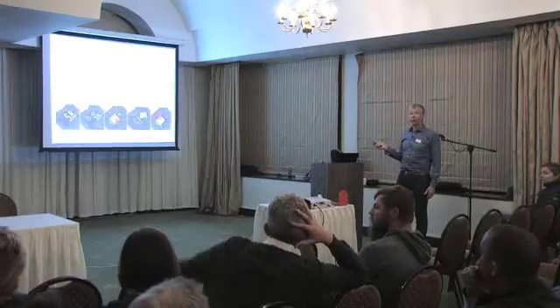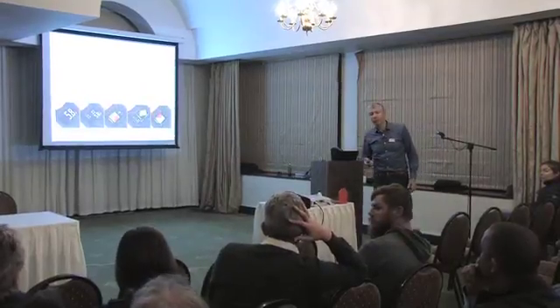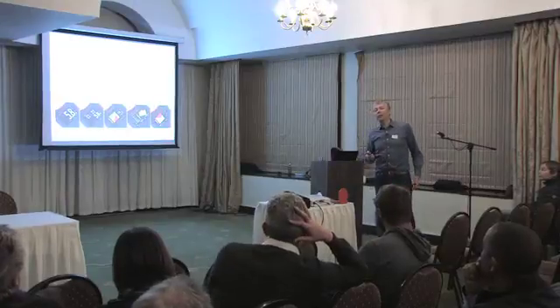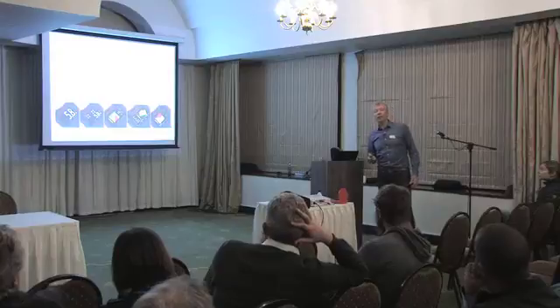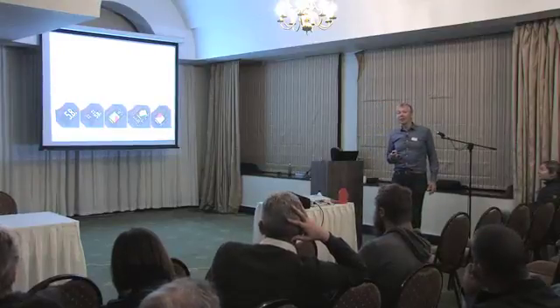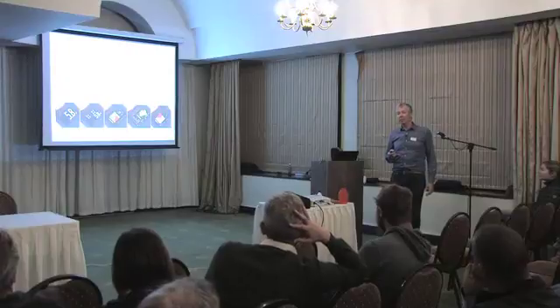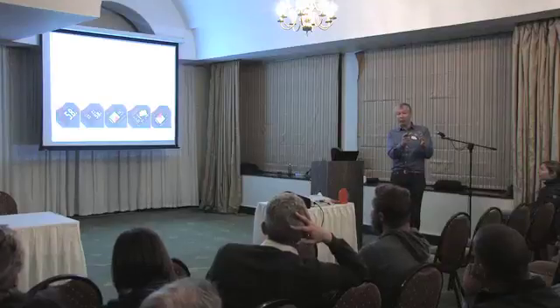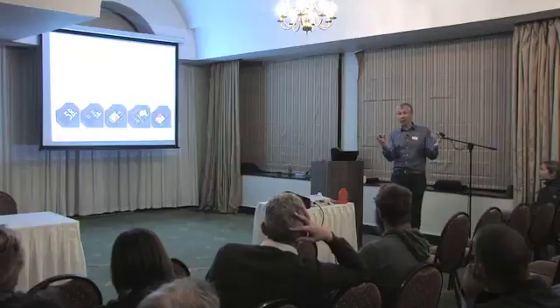Sorry, is it self-verified then? Do you need to send the machine in for calibration, or can you do it with? Oh yeah, yeah. You can send the machine in for calibration. No, I don't want to. Can I verify the accuracy myself with the tiles? Yeah, the tiles have a known level of conductivity. Is it a NIST certified tile? Yeah, fully certified. Yeah, fully traceable certification.